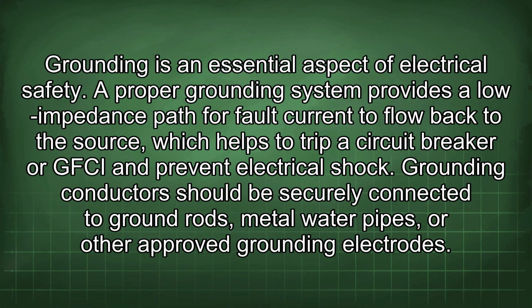Grounding is an essential aspect of electrical safety. A proper grounding system provides a low impedance path for fault current to flow back to the source, which helps to trip a circuit breaker or GFCI and prevent electrical shock.